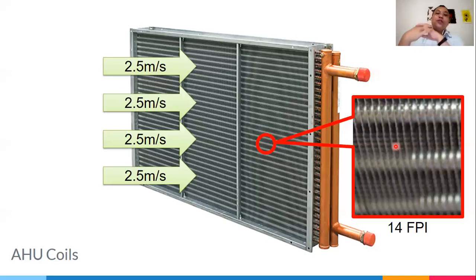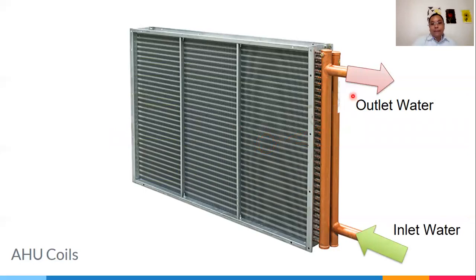So usually, no, pagka hindi ka nag-specify, unless you specify to your coil manufacturer, the default setting of your AHU manufacturer will be at 2.5 meters per second and 14 fins per inch. Ito yung default numbers. Unless you specify to them that I need this fins per inch, I need this velocity, ito yung ibibigay sa'yo ng AHU manufacturer ninyo. So at least you have an idea what size your AHU will be and how deep your coils will be. Okay? Okay.